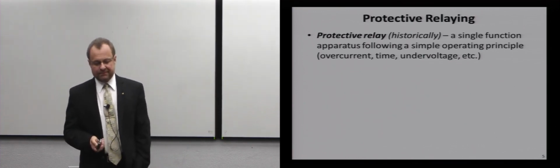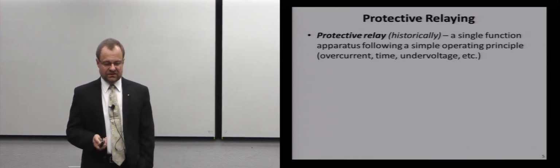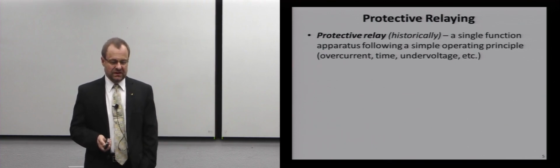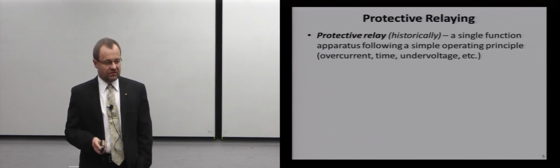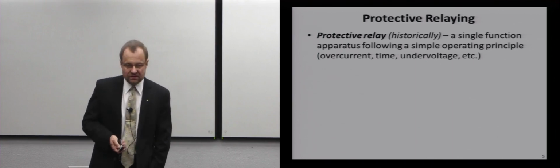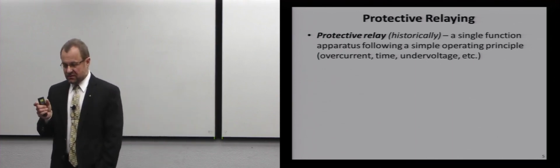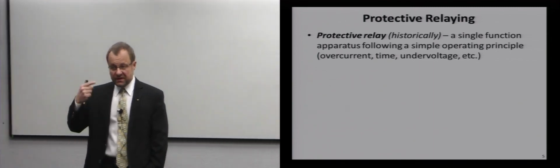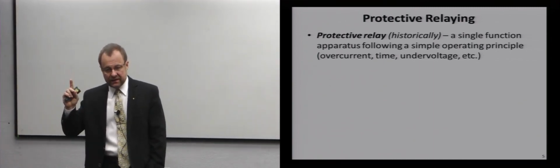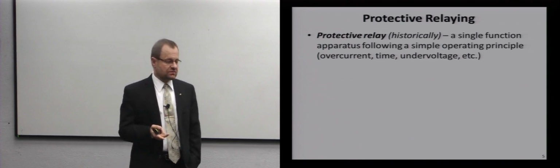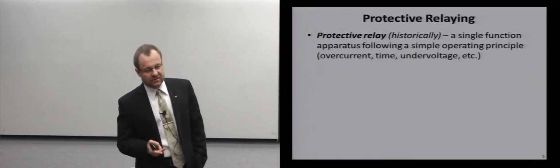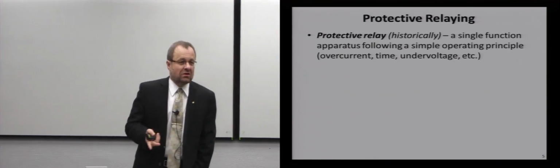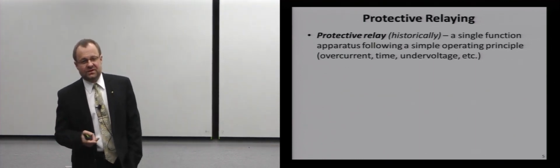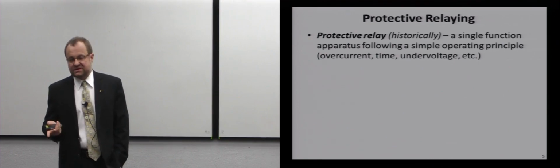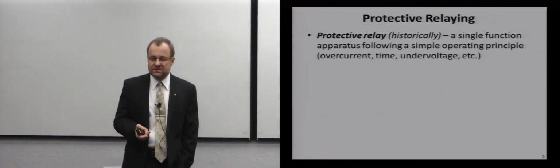Now, what is protective relaying? Historically, a protective relay was a single function apparatus that followed a simple operating principle, such as overcurrent or overvoltage or undervoltage, meaning that if you applied a current to a connection to a relay and you went above the pickup value, the contacts would click. Today, you used to see those relays in cars. Right now, they are phased out because they are replaced by power electronics, by solid-state switches, right? But historically, that was a relay.